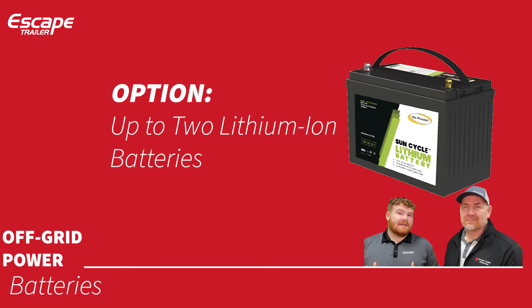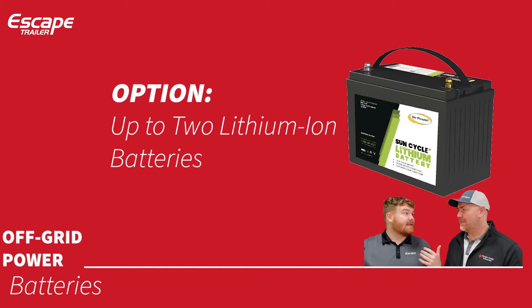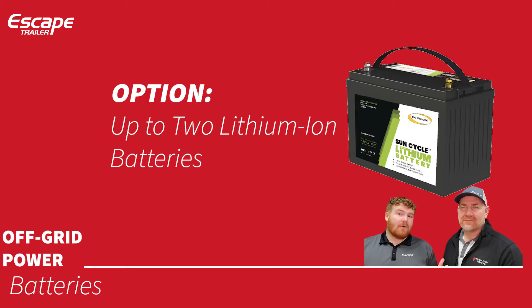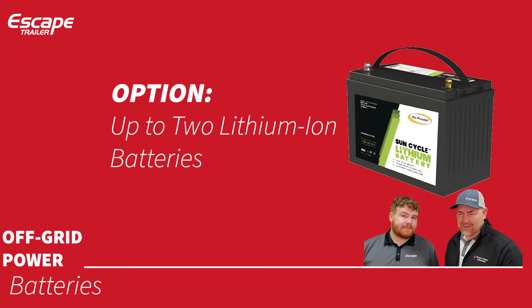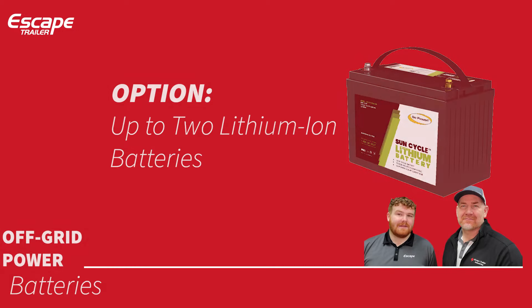Lithium batteries can theoretically discharge to zero percent, but we recommend staying around 30%, giving you 70 usable amp hours from each 100 amp hour battery. You can get up to two lithium batteries. The main benefit is they last so much longer than lead acid. More power, less maintenance, and better longevity — so run on lithium.